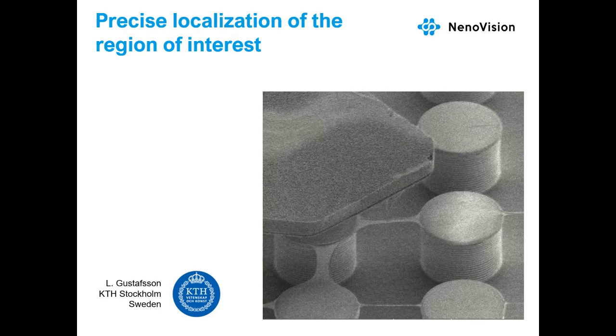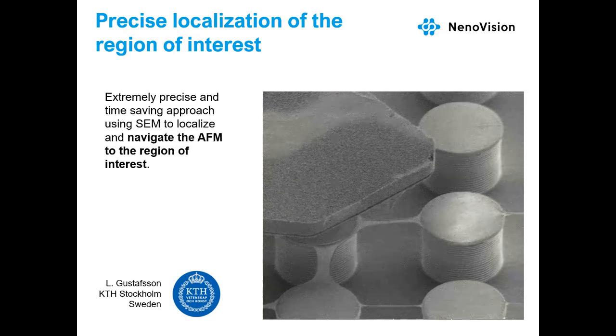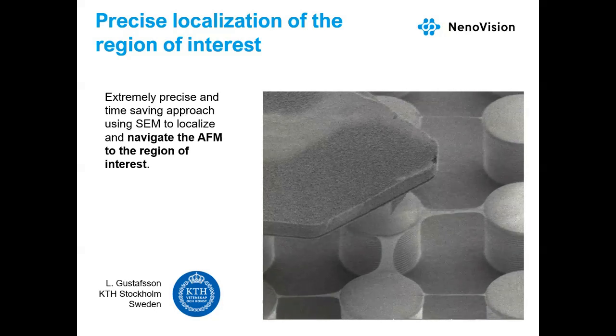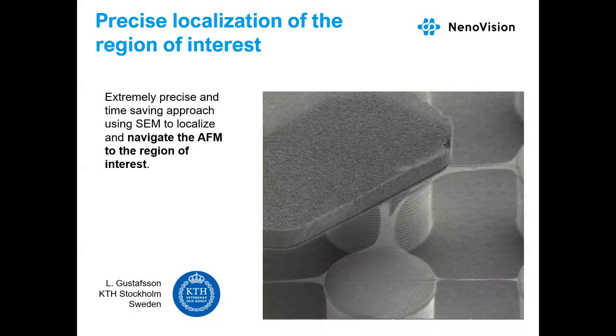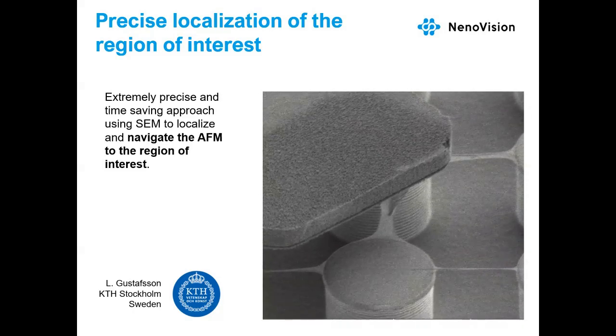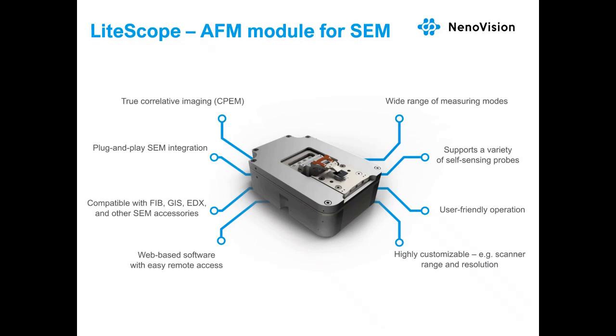Another benefit is extremely precise localization of the area of interest and tip navigation, because thanks to SEM resolution and tip visibility you can navigate to the exact spot while saving a lot of time. The CPEM technology makes it very easy to integrate AFM inside SEM — we call it plug-and-play SEM integration.